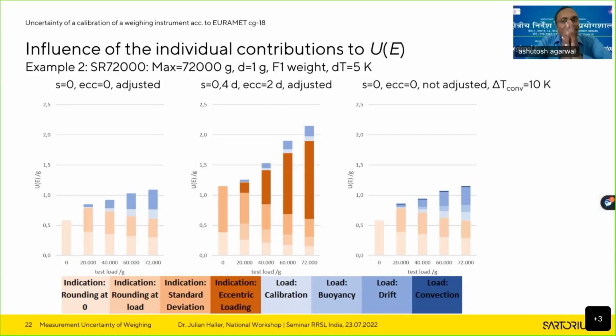Okay. So one very good question. If a balance is 100 kg with a d value of 10 gram, if we keep 50 kilogram on the balance, then what is the acceptance criteria for it? Yeah, so maybe that's the same answer as before, actually. If it is a legal metrology balance, then you would have a class, you would have an e value, you can calculate the MPE, and it would probably be 5 gram or 10 gram, sorry. Yes. Then it's clear. If you have an application or a weighing instrument outside of legal metrology, then it really has to be defined by the user.